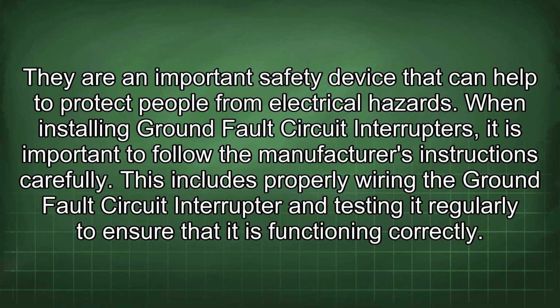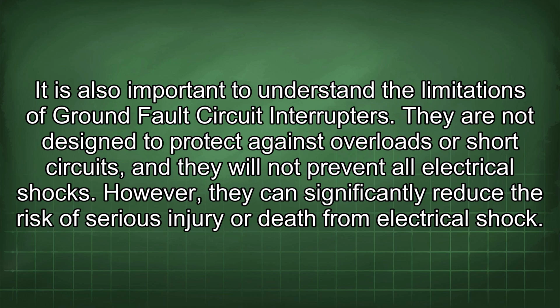When installing ground fault circuit interrupters, it is important to follow the manufacturer's instructions carefully. This includes properly wiring the ground fault circuit interrupter and testing it regularly to ensure that it is functioning correctly. It is also important to understand the limitations of ground fault circuit interrupters. They are not designed to protect against overloads or short circuits, and they will not prevent all electrical shocks. However, they can significantly reduce the risk of serious injury or death from electrical shock.